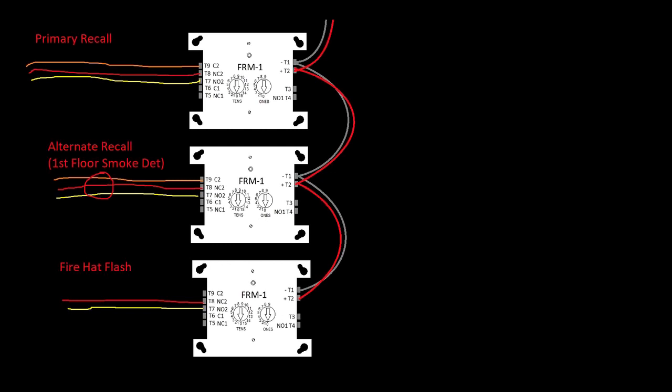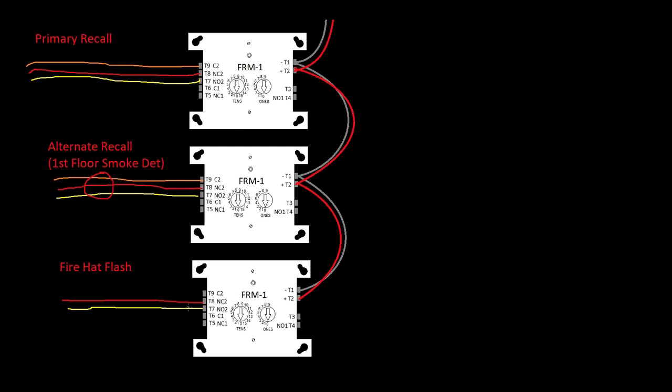Okay, so we're going to do that for all three. And then you're going to have to find out from them, like I was just saying, when my primary - I'll send this question to people in emails to try to get it answered ahead of time, but it's such a simple fix that if you have to change it even the day of the test it's no problem. But I will ask them: when my fire hat triggers, do you want just the fire hat relay, or do you want the fire hat relay and the primary or alternate, depending on the floor, to trigger?